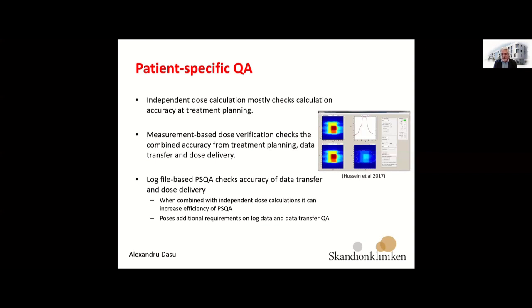And this is something that is subject to very much research nowadays: the combination of log file analysis with independent dose calculation in order to see what has been the predicted dose in the patient. This has also found advantages, for example, in adaptive treatment, where you could assess whether the intended dose has been given, and if not, take some action, or if you see, for example, that the anatomy of the patient has changed significantly, adapt the treatment. However, log file-based patient-specific QA poses additional requirements on log data and data transfer. And then you have to do a QA that the log data is relevant, and that the data transfer, for example, from the log file to your analysis system has been performed very well.